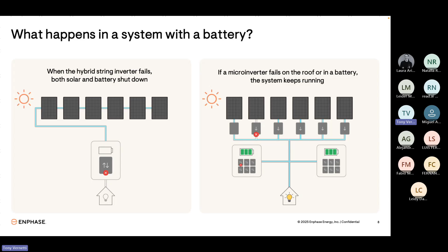Now, the Enphase system has an added layer of reliability as well, which we call sunlight jumpstart. Now let's talk about hybrid inverters for a moment here. With hybrid inverters, if the battery gets totally depleted, they're not actually able to start up the solar system the next day.